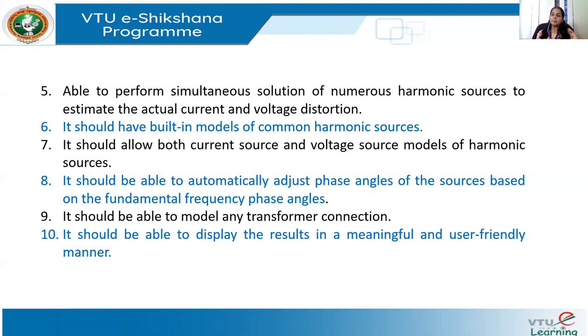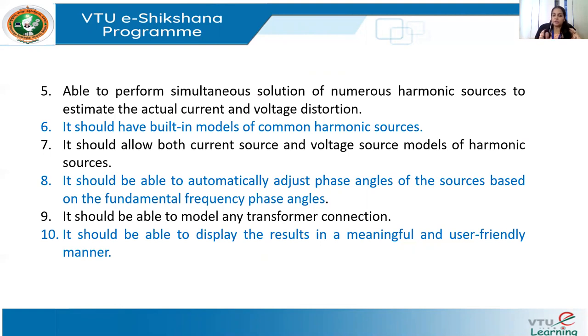The system should have inbuilt models for harmonic sources, since we cannot manually model every power electronic converter or nonlinear load. If the computer program has inbuilt models for nonlinear or harmonic sources, it becomes much easier to use. It should also have current source and voltage source models for harmonics, since nonlinear loads sometimes need to be represented as a current source and sometimes as a voltage source. Additionally, it should automatically adjust the phase angles of sources based on the fundamental frequency phase angle.